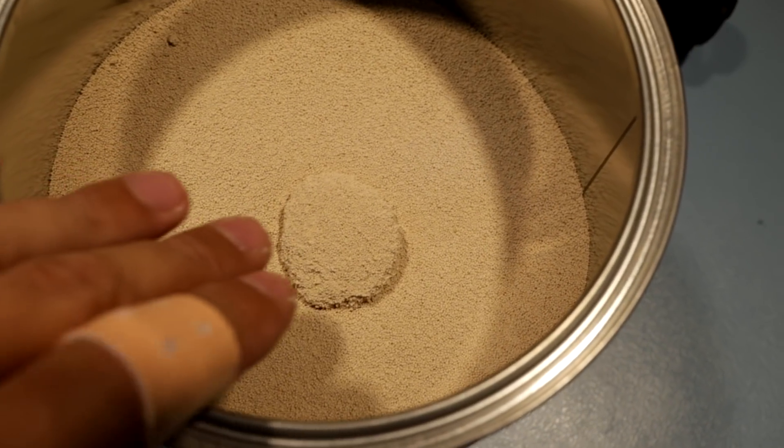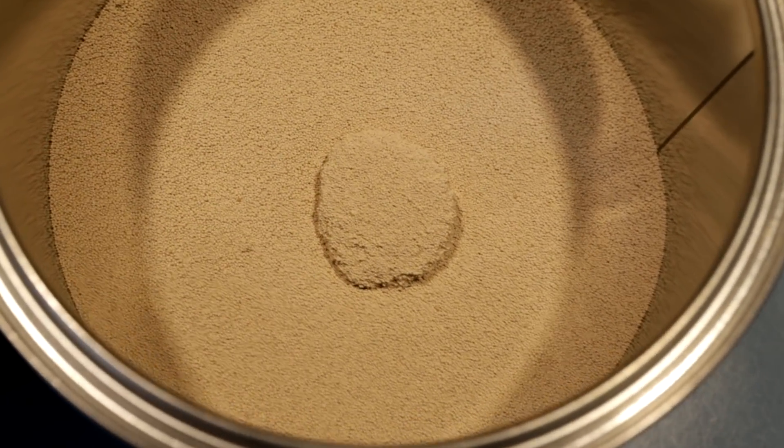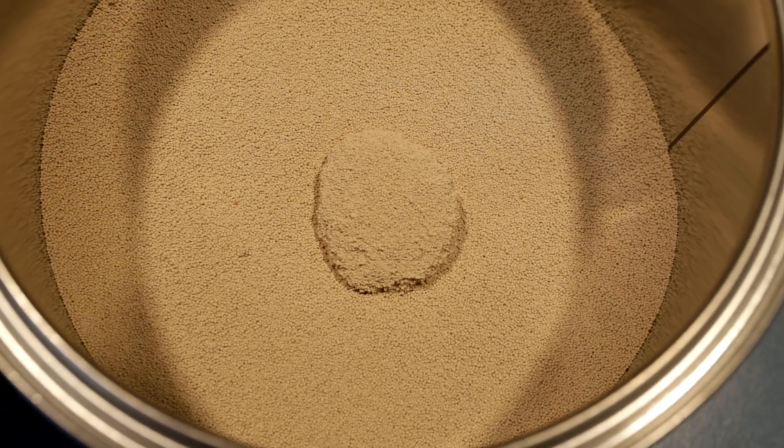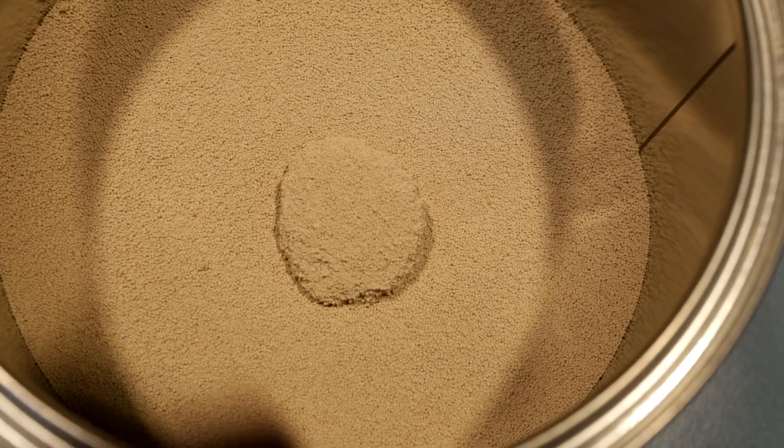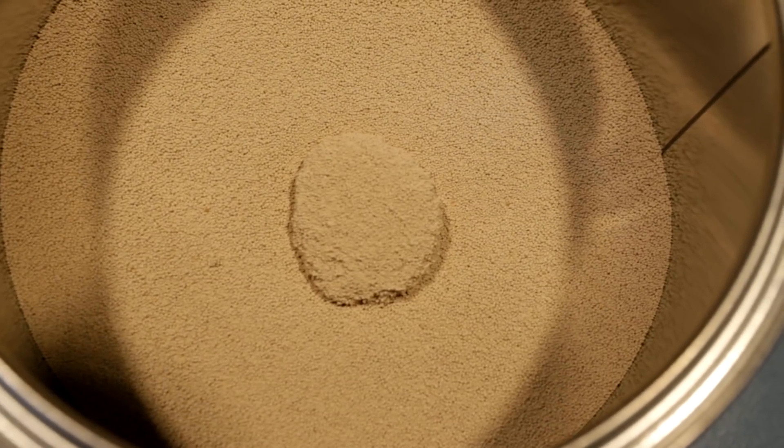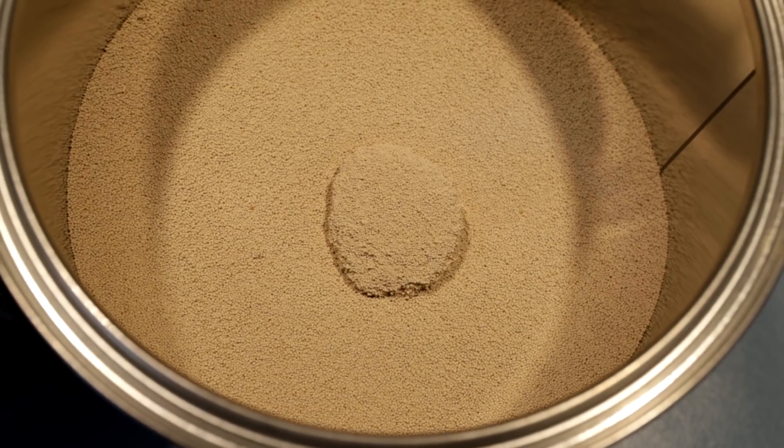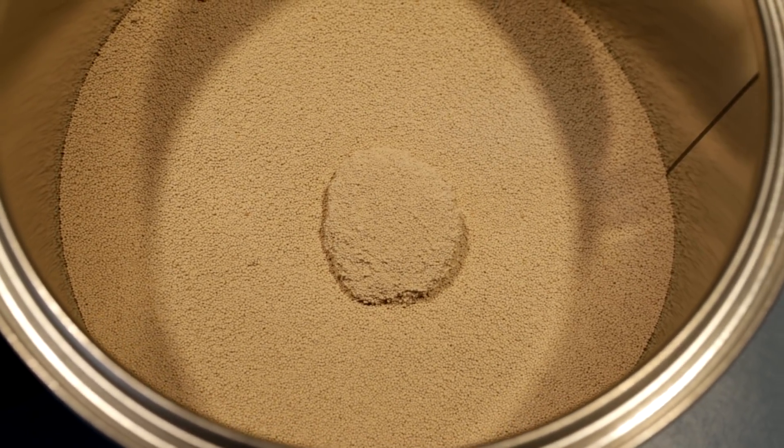You can see here we have lumps of the zeolite, and this probably indicates that we had too high humidity in the system, so it was condensing and forming these lumps. This might be the problem why we had so low oxygen concentration on these cylinders.